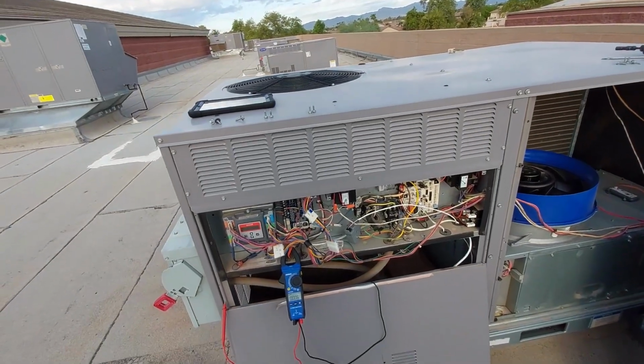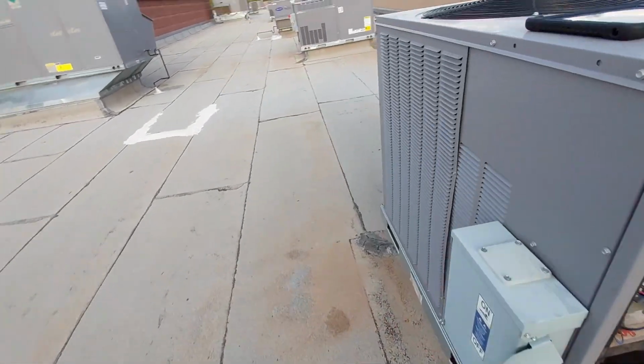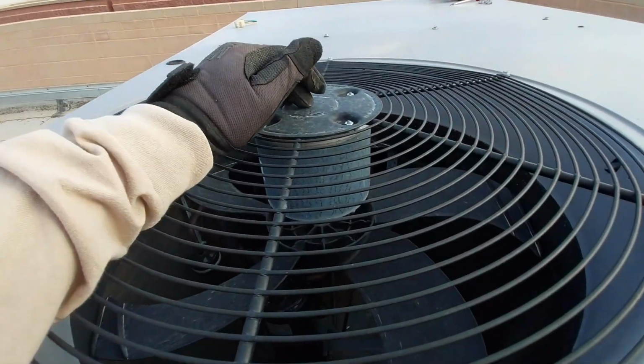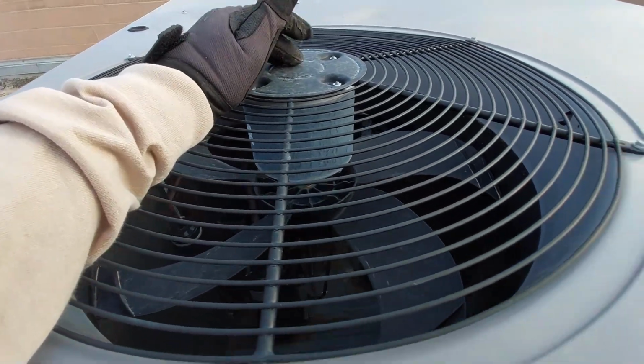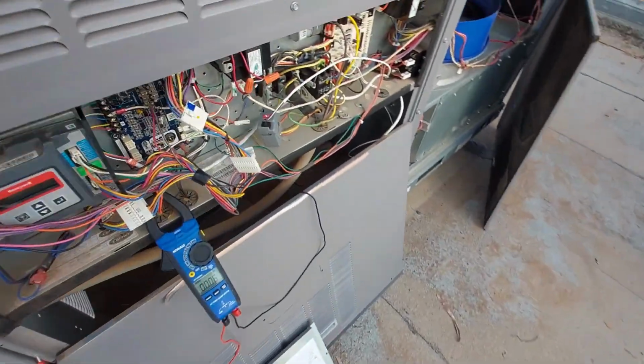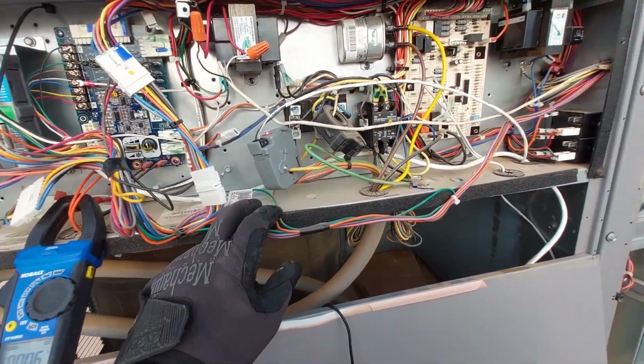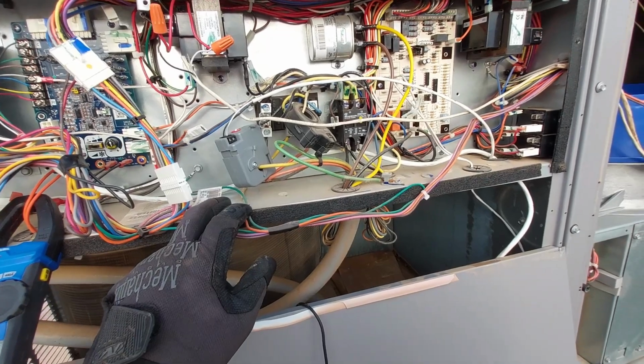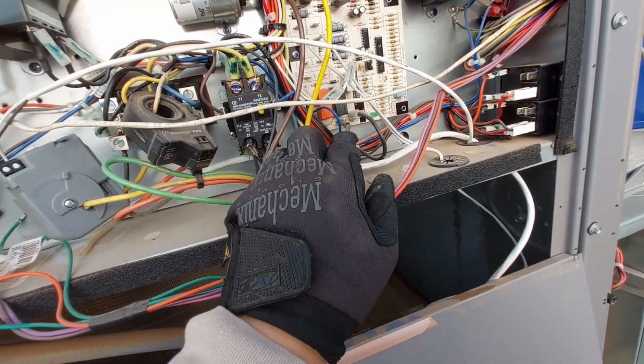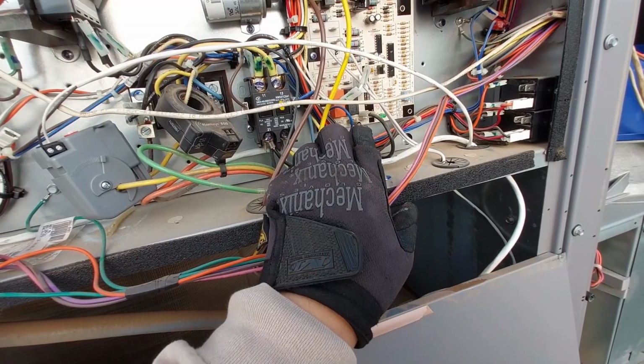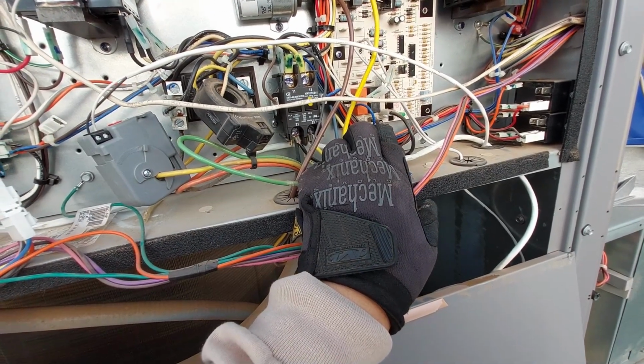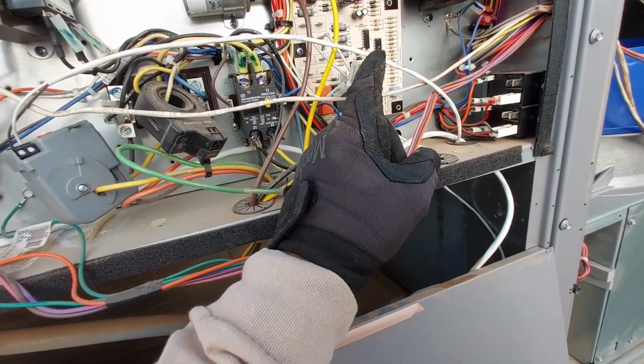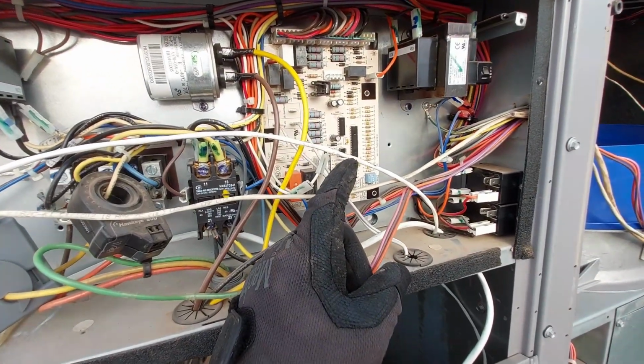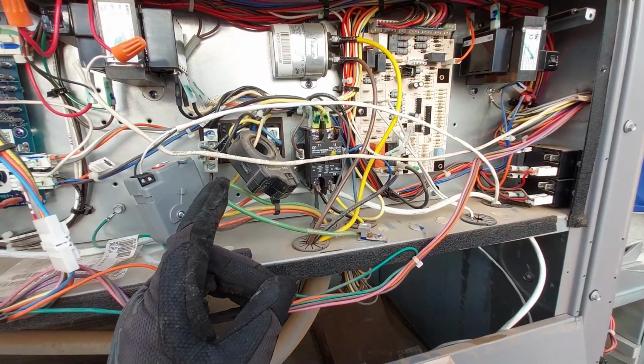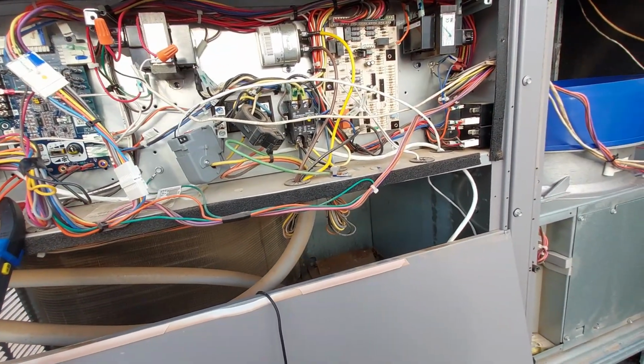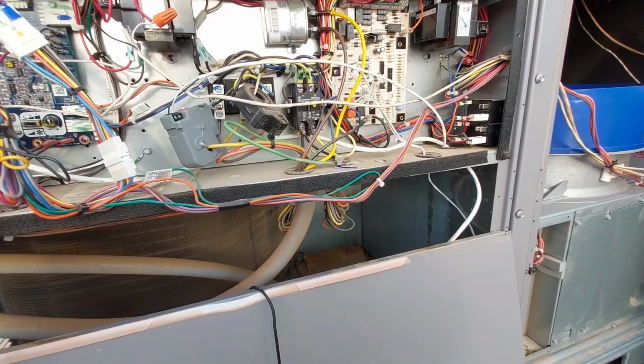That could be the issue here as well, that the condenser fan motor has just gone bad. Or it could be somewhere here in the wires where it's just not sending over voltage, because this is my wire for the outdoor fan motor. I should check if it's getting voltage. I will check that, see if that's the issue. Maybe it's not getting low voltage, and maybe this board here is the issue, which is causing the compressor to overheat if that condenser fan motor is not coming on. So yeah, plan B.